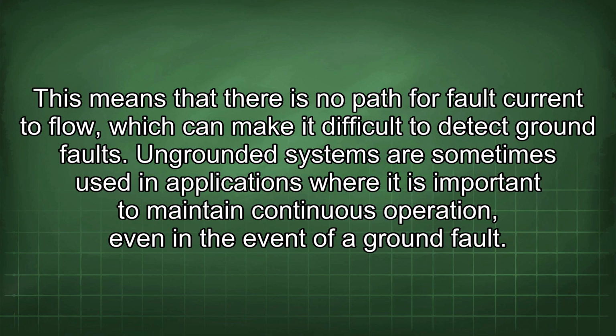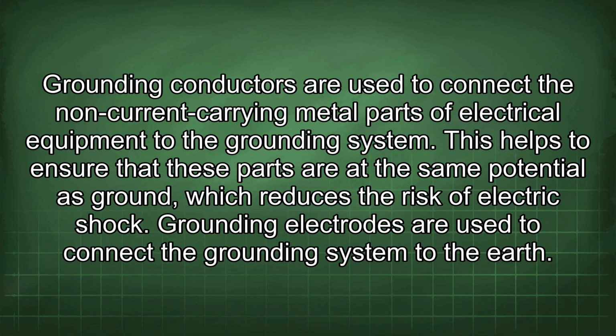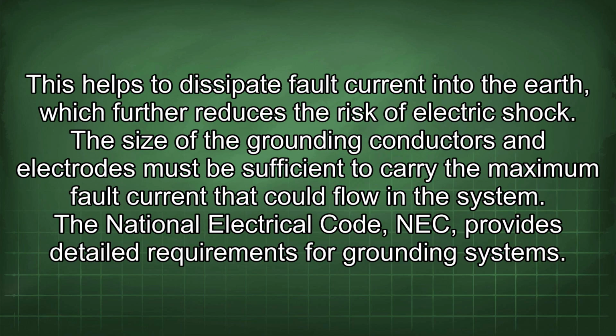of a ground fault. Grounding conductors are used to connect the non-current carrying metal parts of electrical equipment to the grounding system. This helps to ensure that these parts are at the same potential as ground, which reduces the risk of electric shock. Grounding electrodes are used to connect the grounding system to the earth. This helps to dissipate fault current into the earth, which further reduces the risk of electric shock. The size of the grounding conductors and electrodes must be sufficient to carry the maximum fault current that could flow in the system. The National Electrical Code (NEC) provides detailed requirements for grounding systems.